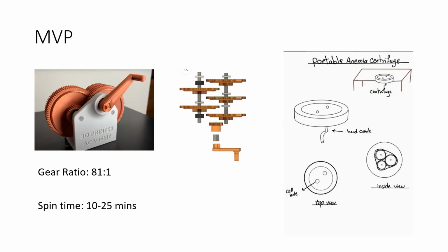Our design is a hand crank centrifuge that can spin at high speed without electricity. The main components are a handle to power the device by hand, a gearbox to increase rotation speed, and a top panel to hold 2 vials of blood samples. The user will rotate the handle at about 50 revolutions per minute for 10 to 25 minutes.